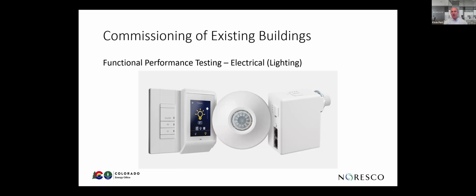There's also another big change in daylight responsive controls in the code. The general lighting wattage allowance is now cut in half for when you need daylight responsive controls. So any space with 75 watts of lighting in a daylight zone now needs to have daylight responsive controls. It used to be 150 watts.